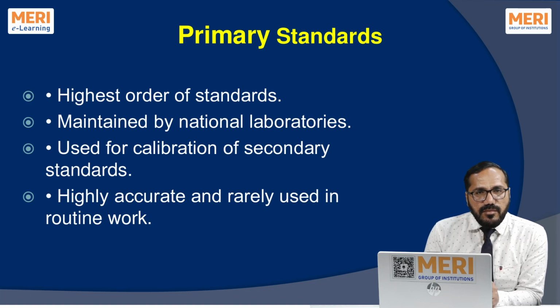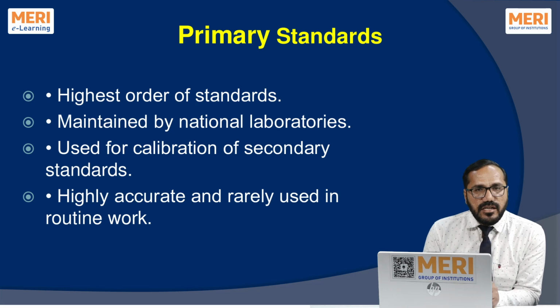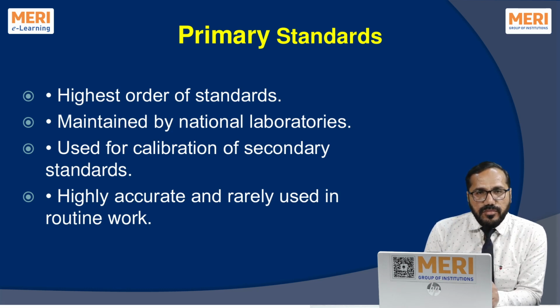Primary standards. These standards are the highest and most accurate standards of measurement available in a country. They represent the ultimate reference for a particular physical quantity such as length, mass, time, or temperature. These standards are maintained by national metrology institutes such as the National Physical Laboratory in India or similar national institutions in other countries. These institutes are responsible for maintaining and improving the country's measurement system. Primary standards are maintained under highly controlled environmental conditions. The temperature, humidity, air pressure, and even vibrations are carefully controlled because small environmental changes can affect the measurement accuracy. For example, even a slight temperature variation can cause the expansion or contraction of materials, affecting the dimensional standards.